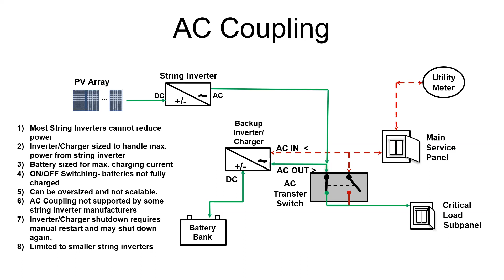But again, all of that energy that's being produced by the array has to go somewhere, and it has to go into the battery bank. Now, when you're just all of a sudden shutting off that nozzle, just like shooting a fire hose into a bucket, you're not really going to have any good sense of awareness as to when that water level is getting close to the top. You're going to turn it off. It's either going to overflow or it's going to stabilize. And when the water subsides and reaches a constant level, it's going to be at 80% full, which is not good for maintaining batteries for a prolonged lifespan. You want to get them to that 100% state of charge occasionally. And we'll show you why DC coupling is a much more effective way of doing so.